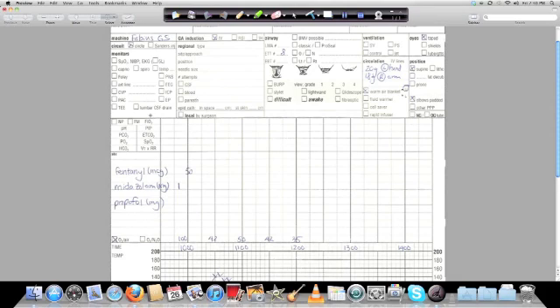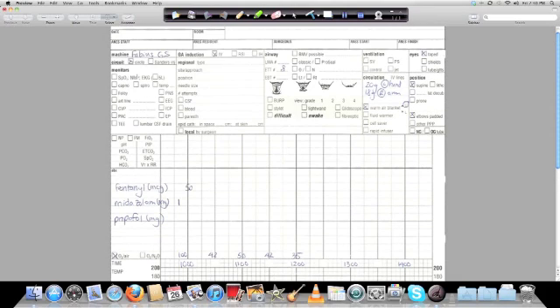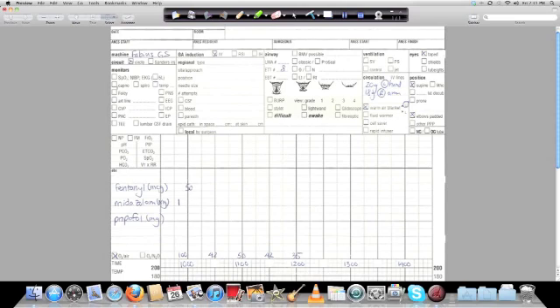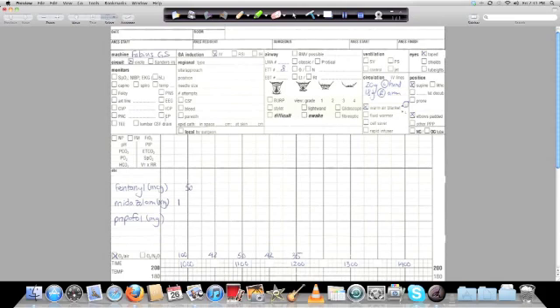Then we move over to the monitors that you've put on the patient, what parameters are going to be monitored during the operation today. So, pulse oximeter, 5-lead ECG, capnography, spirometry, temperature, do they have a Foley catheter in, do they have an arterial line, do they have a central line, are you monitoring their intracranial pressure at the same time. You tick off which ones these patients have and that serves as a record of that.